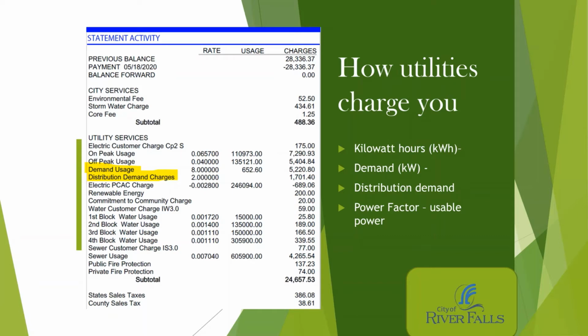The next one is the distribution demand, which has a lower charge—$2 per KW. The distribution demand is your highest demand spike over the last 12 months, and we carry that forward every month, so you pay for that highest spike. We do that because we need to size our equipment accordingly.